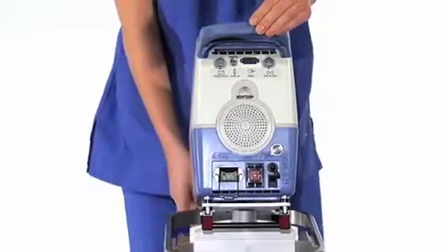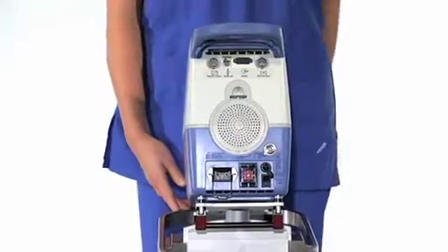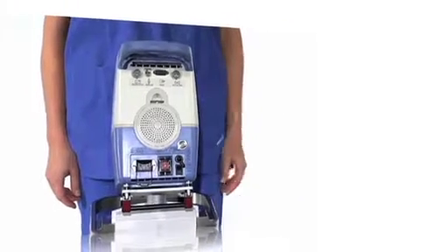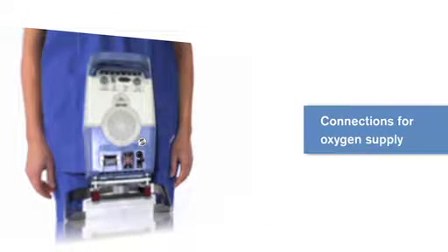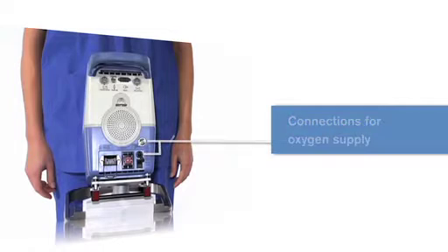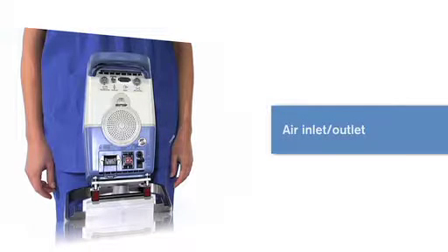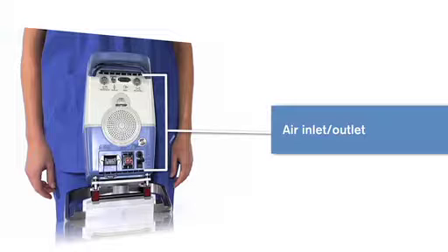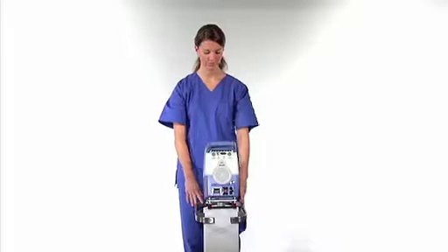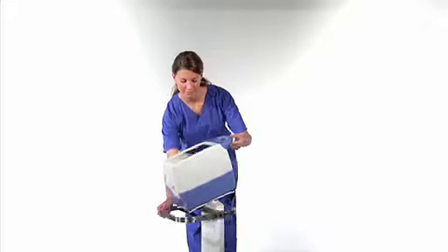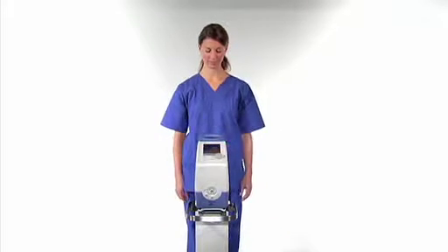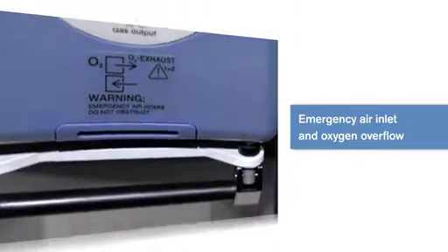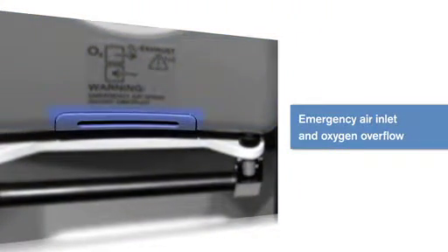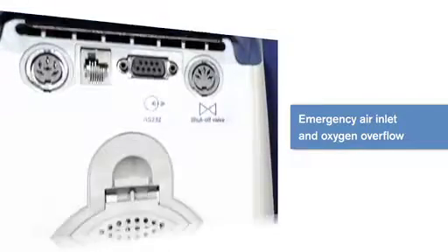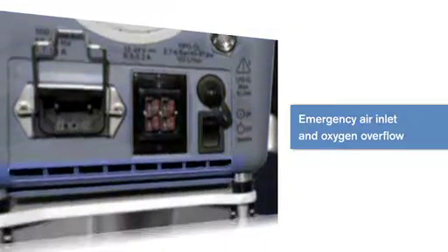The Carina has an integrated turbine, so an air supply is not needed. Additional oxygen can be added if required. There are various air inlets and outlets around the device which need to be kept clear of any obstructions. Ensure there is a space of at least 20 centimeters or 8 inches between the device and any other objects. The emergency air in and outlet and oxygen outflow are built into the upper and lower parts of the front and back panels. Do not cover these openings.